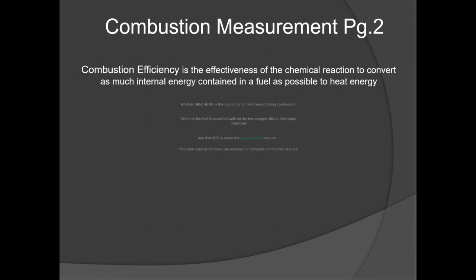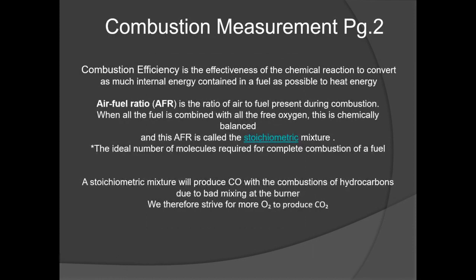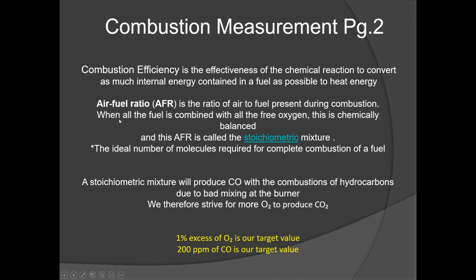Some terms to clear up before we get going. Combustion efficiency, by definition, is the effectiveness of the chemical reaction to convert as much internal energy contained in a fuel as possible to heat energy — we're trying to get the most bang for our buck out of the fuel we're providing. Air-fuel ratio is the measure we use when talking about combustion efficiency. It is the ratio of air to fuel present during combustion. When all the fuel is combined with all the free oxygen and it's chemically balanced, this air-fuel ratio is called the stoichiometric mixture.